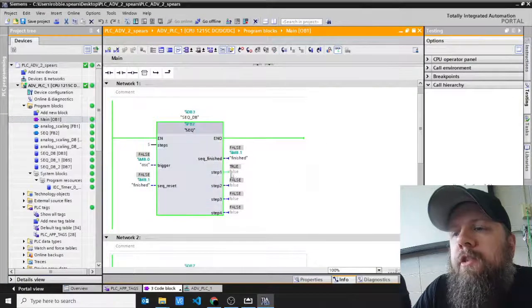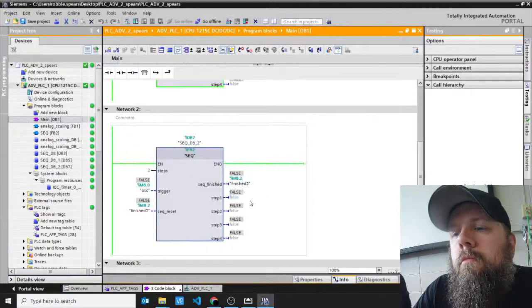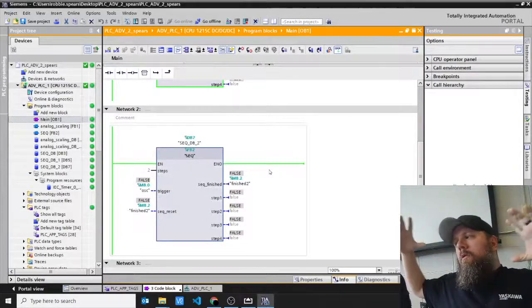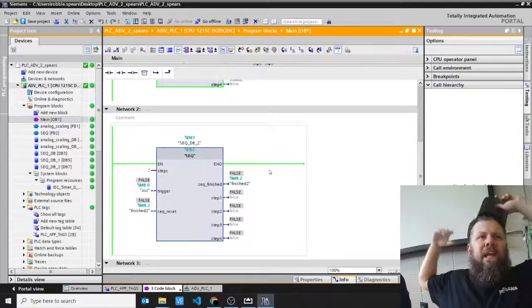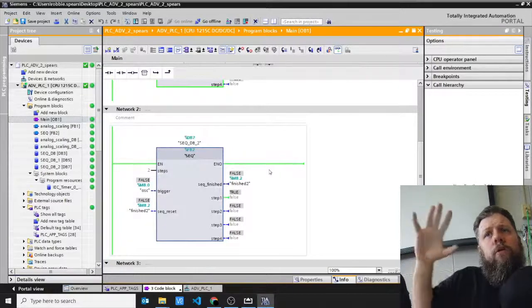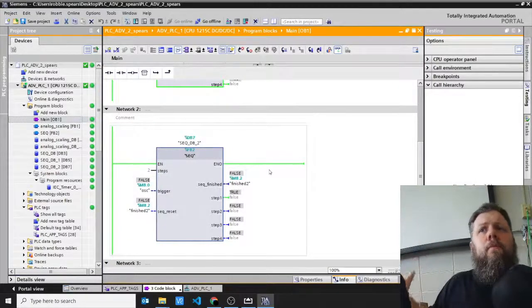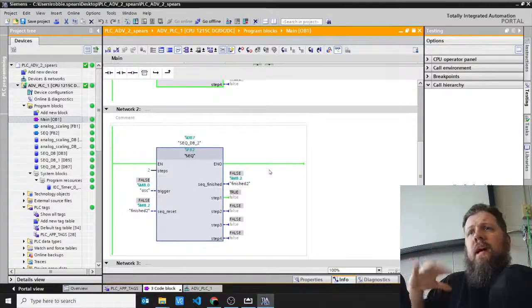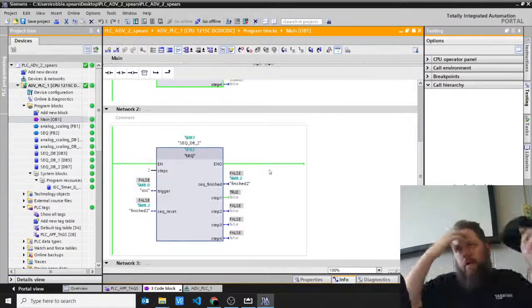Okay, so sequencer 1 is going all the way through those, right? Sequencer 2, boom, boom, is just going through its piece. All right, so if you're going to use anything that has an instance in it, that needs its own memory, but you're going to reuse it over and over again, put multi-instance because you don't want it overriding the same memory data block over and over again, okay?